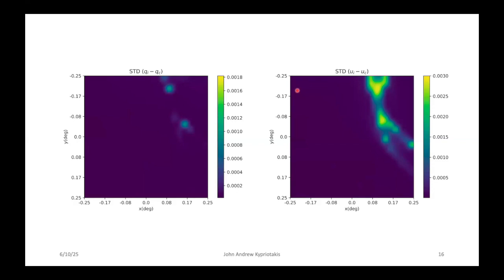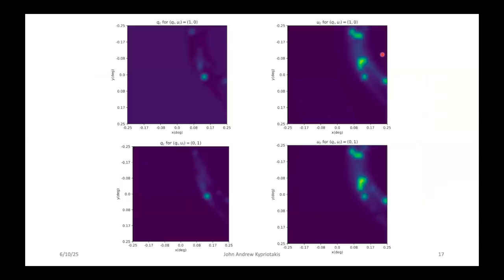We then move on to the standard deviation of the calibrated minus the theoretical, the retrieved parameters. And let me remind you, this is a noised model. You see in the left and in the right, we are very, very low in the standard deviation that we get. So we have a model that does actually perform well, does not have huge tails. You see only one small arc that performs worse, and I will explain this arc in the very next slide, where I'll be showing you the translation plots for the instrument.